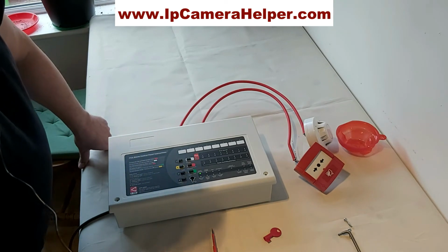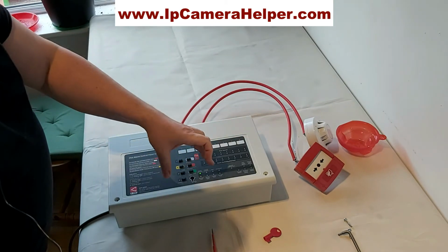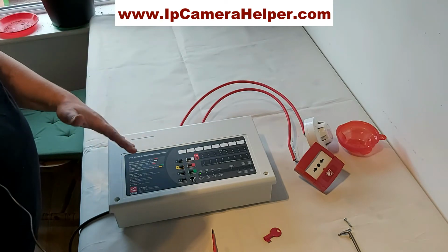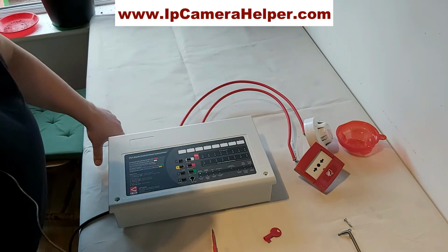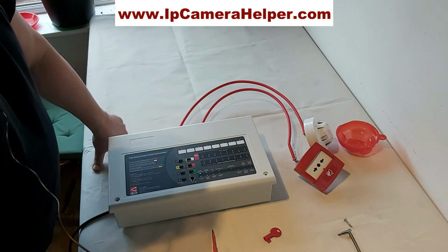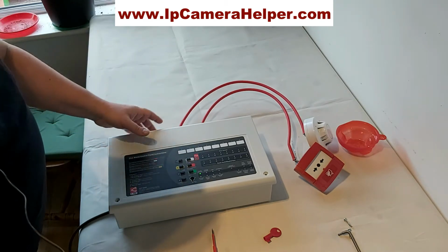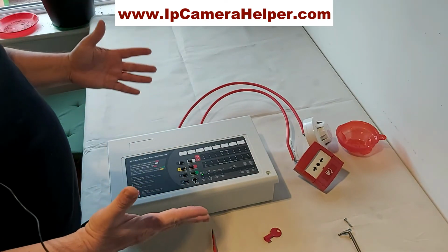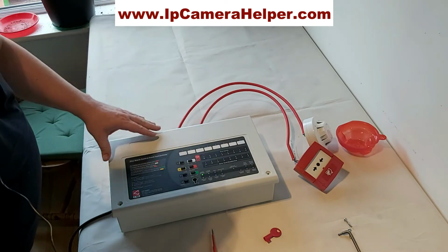And the third function is to send a signal to a monitoring station, which is to trigger an output on this device. In a small installation, usually this output is connected to the intruder panel, and the intruder panel sends a signal to the monitoring station, or you can call it alarm receiving center, through their communication device. Typically fire alarms don't have a communication device. Doesn't mean they cannot, just that's general practice in Ireland and probably the UK.